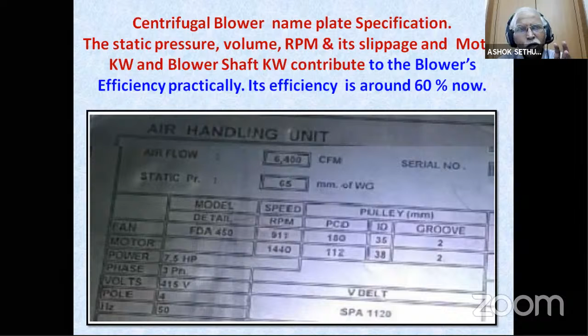This shows the nameplate. It gives a CFM, it gives a static pressure in water column, it gives the motor RPM, it gives the blower RPM, and what is the motor power. Automatically, the brake horsepower also is given here. So automatically the blower efficiency is around 30 to 40% only as a system. The nameplate indicates the efficiency of the blower, and you have to calculate by yourselves.